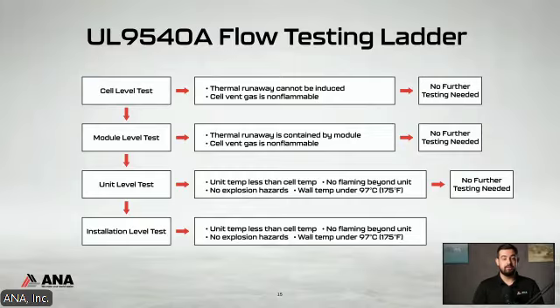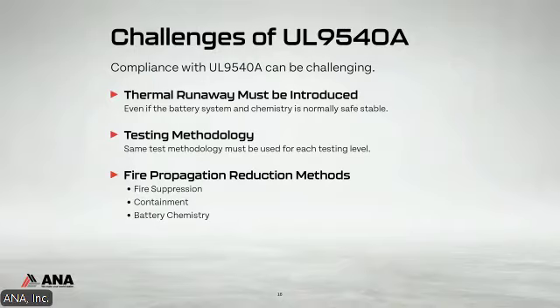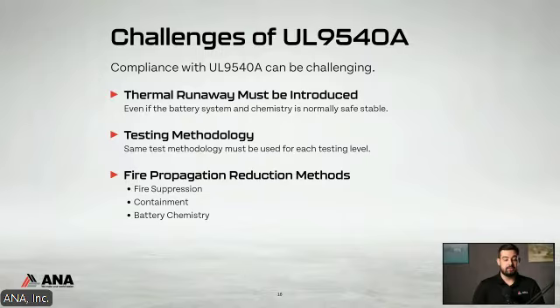This is going to be your battery pack level for fire testing. So, challenges of 9540A now. Thermal runaway must be induced. Like I said, they're going to try everything they can to get your cell or your pack to fire propagate. As of right now, the standard is written so that you must do everything you can to get it into thermal runaway. The testing methodology is something to consider. So if you use a high ambient test, let's say 70C for your cell level testing, you must induce the thermal runaway in the exact same format as you move on the ladder. So module level, unit level, you will have to induce thermal runaway at that same testing specification, right? So you will have to test that 70 C ambient again.